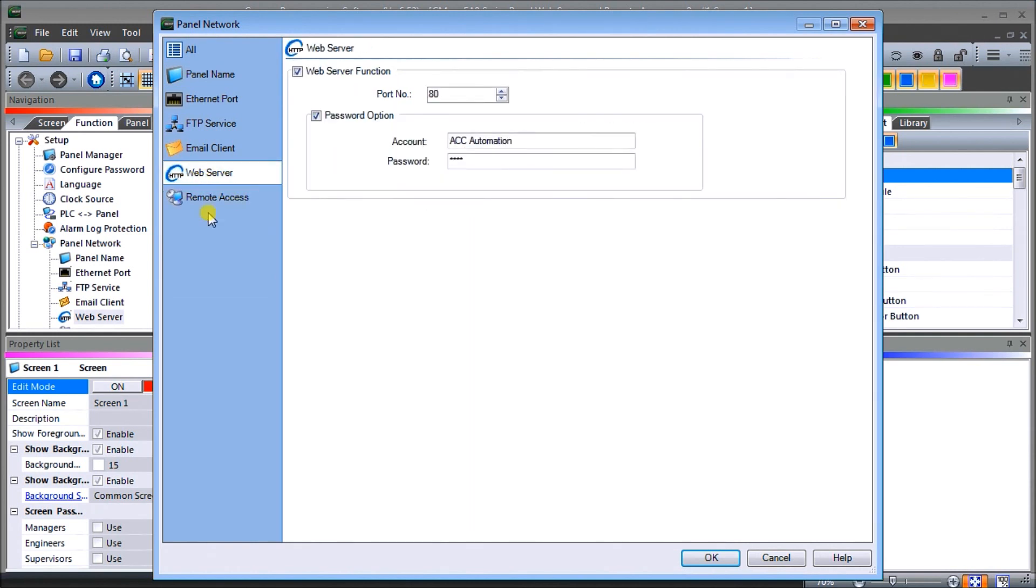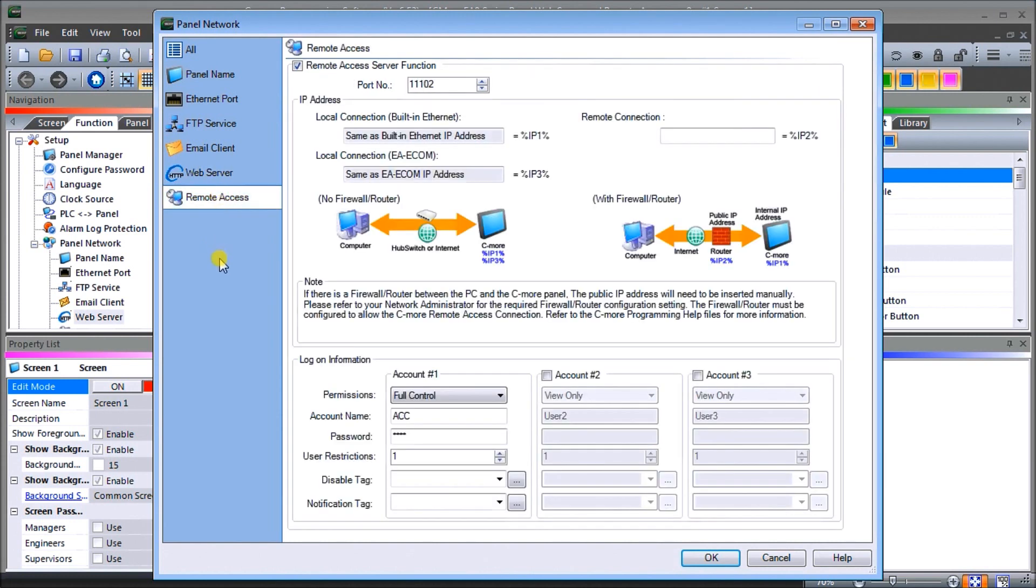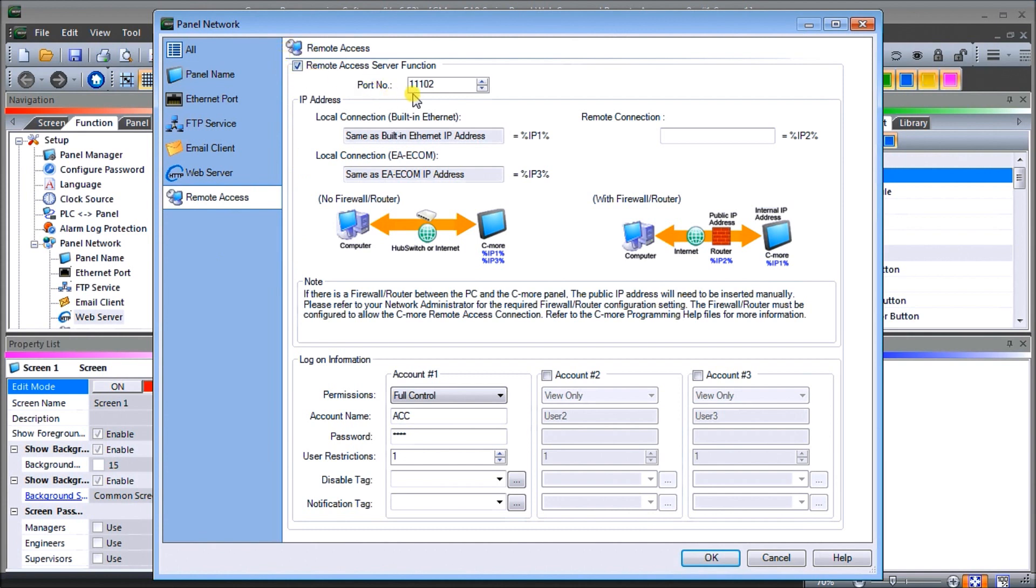One difference is the web server itself is going to give static information and we can create a website that operators or management can go to and find information or download files. The remote access will allow us to actually access the information on the HMI that we've programmed already and control it remotely. We're going to enable the remote access feature. The port number is going to be 11102, we're going to leave that as default. This is the same Ethernet port as our built-in Ethernet that we have already.